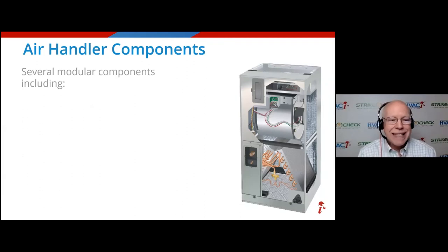All right, let's go inside and talk about an air handler. And notice now I am showing a straight cool or an air handler unit only. And that looks different than when I showed you earlier, when I showed you a furnace. This one has no heating components in it, and they've rearranged the items. In a straight cool air handler, most times they put the evaporator coil at the bottom, called an integrated coil, and the blower at the top. Whereas if you have a furnace, the blower's normally already built in at the bottom. They add a cased coil on the top of the furnace.